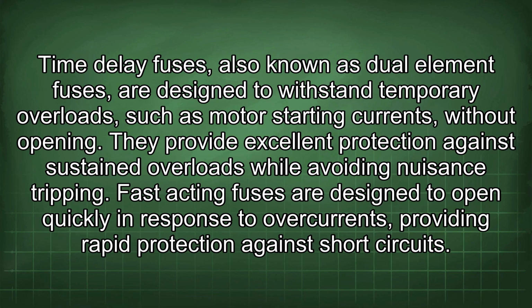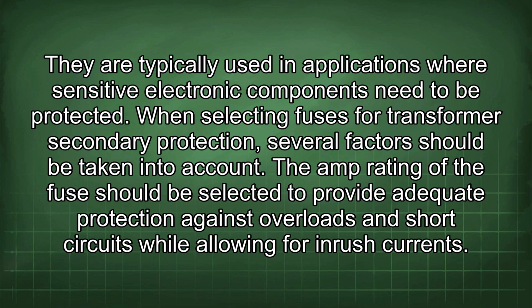Fast-acting fuses are designed to open quickly in response to overcurrents, providing rapid protection against short circuits. They are typically used in applications where sensitive electronic components need to be protected. When selecting fuses for transformer secondary protection, several factors should be taken into account.